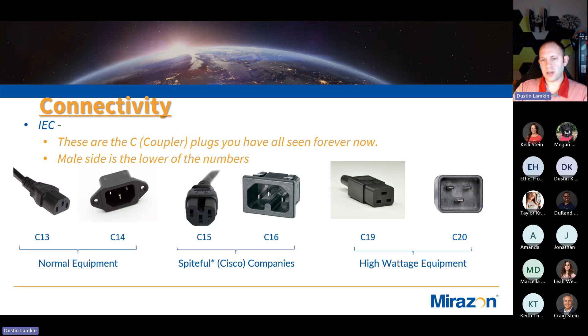Then you get into the higher wattage equipment. We've got C19 and C20 connectors now. These are rated for 20 amps as opposed to 15, so a lot of times with UPSs and PDUs you'll see these C19, C20 connectors. Just a note, these are all North American ratings. If you leave the country you need to look it up, since North America is the least conservative country as far as these ratings go. So while the C19 and C20 is rated for 20 amps here, it might be 15 in the EU or South America, different places. We just have to be cognizant of that if we're doing international work.